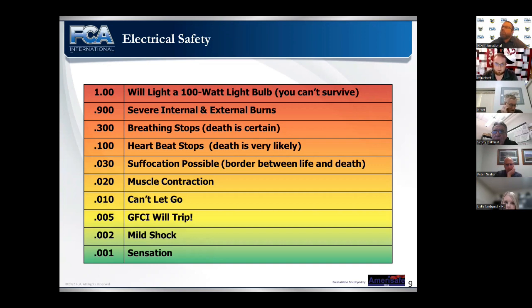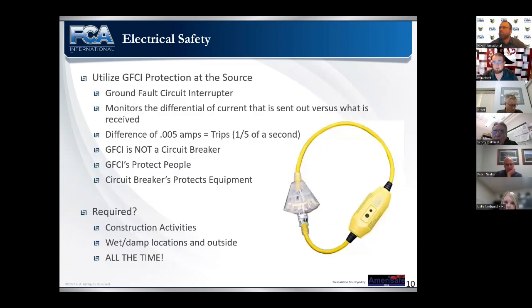Circuit breakers are designed to protect the electrical system and stop your house from burning down. They're not meant to protect people, except for the people in the house not wanting to get burnt down, right? But they do not protect from shock. What protects from shock is a ground fault circuit interrupter. Ground fault circuit interrupters are designed to trip in 1/5 of a second at 0.005 amps, right? So 5/1000ths of an amp goes and it notices and it will trip. That way, when we have a fault that small, and what a fault means is that the electricity that's going into the system is not flowing back where it's supposed to, it notices that, it trips out, and that's less than a second, and it is designed to protect people.